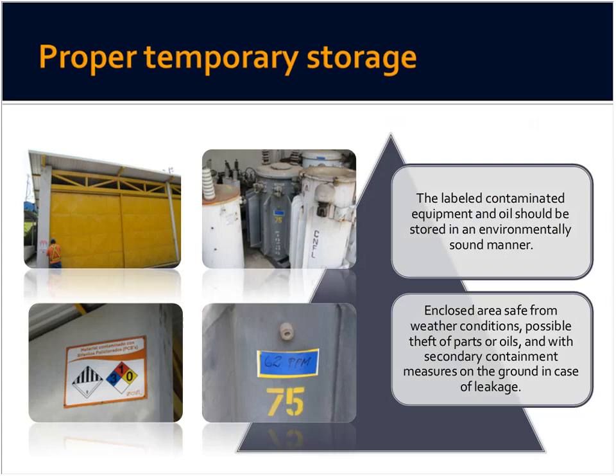The proper temporary storage: once the equipment has been identified and labeled, it should be stored in a proper storing location. It should be sealed off and have a roof. It doesn't necessarily have to be a cement wall; it can be a chain link fence, but it needs proper labeling that inside there is PCB contaminated equipment, that it's dangerous, that it's a possible impact to health. It should be covered with a roof to avoid weather implications, and sealed off with some sort of protective material to avoid people coming in and possibly wanting to take the metals or oils away for selling or whatever.